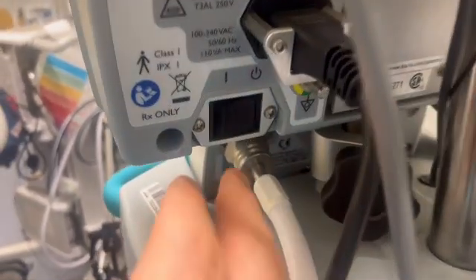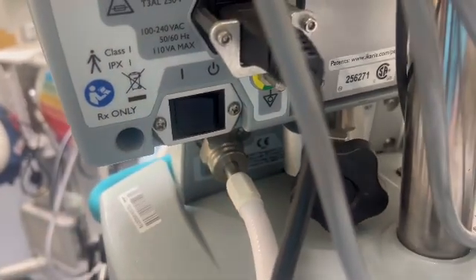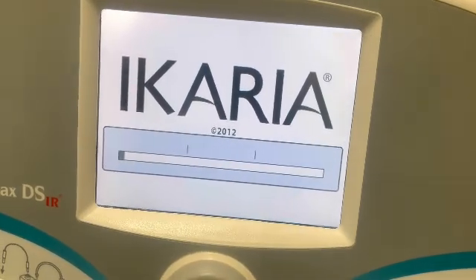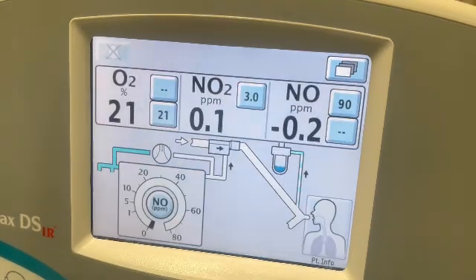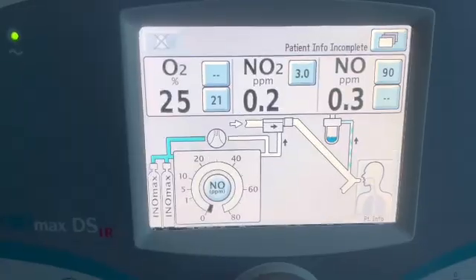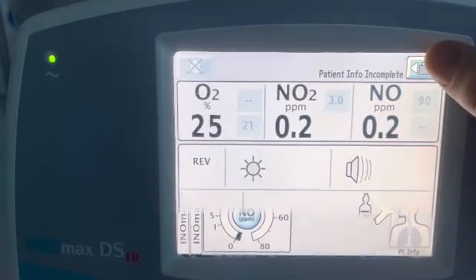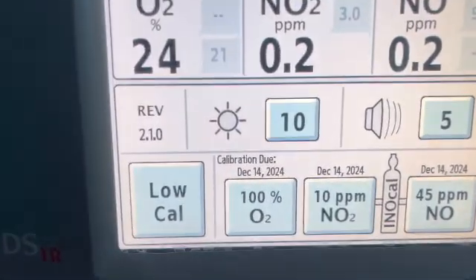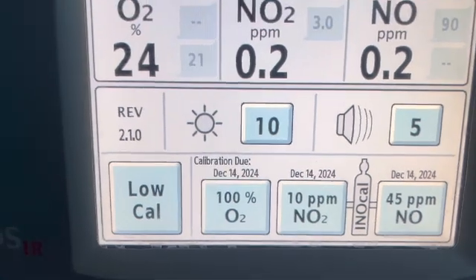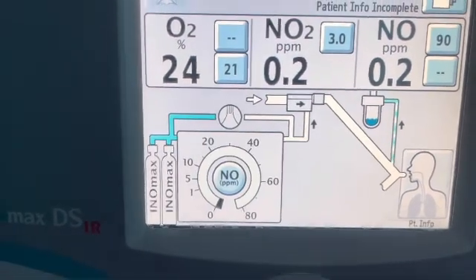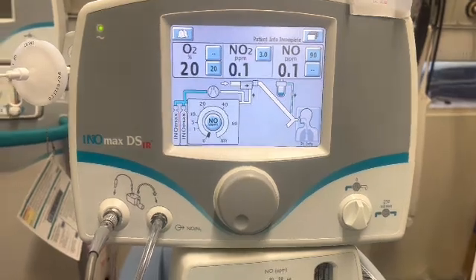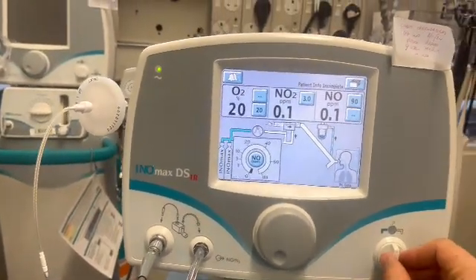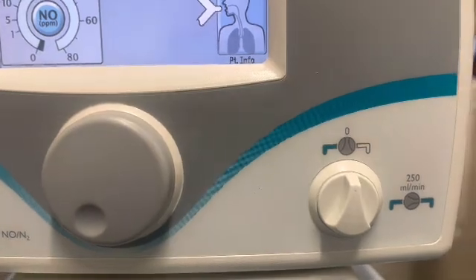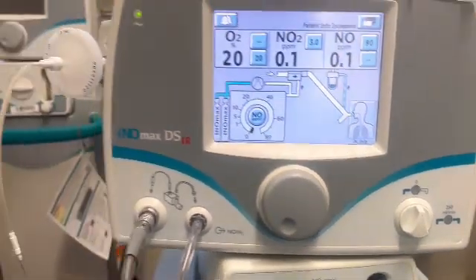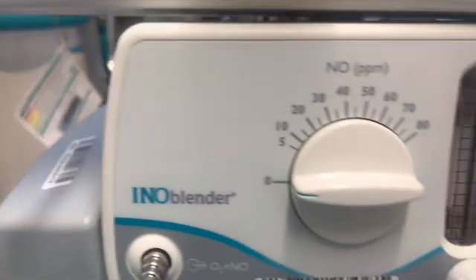The switch can be found easily at the back of the machine. Turn it on. The machine now checks some internal components and boots up. Using the icon on the top right, see when the high-level calibration performed by the intensive care technicians is due. If this is timed out, the machine shouldn't be used. Have a look at the machine. Ensure that the backup delivery switch has not been switched on, so it's on 0. Have a look at the INOblender and make sure it's not been switched on.